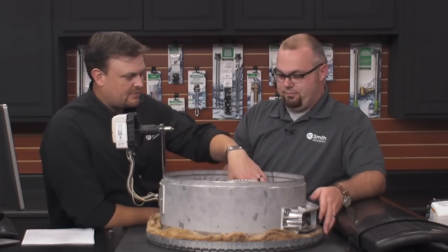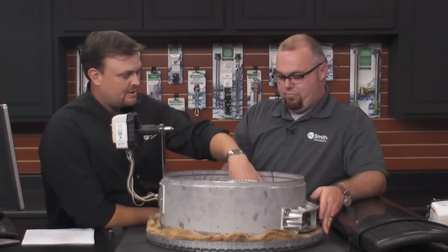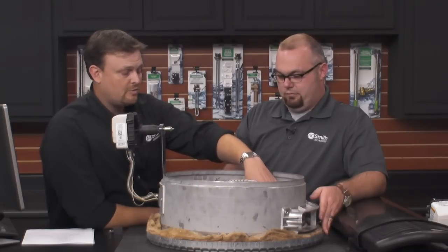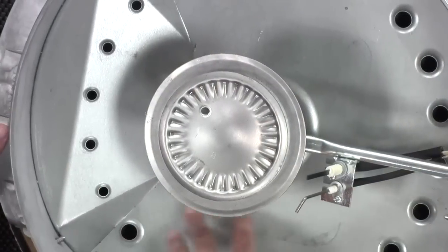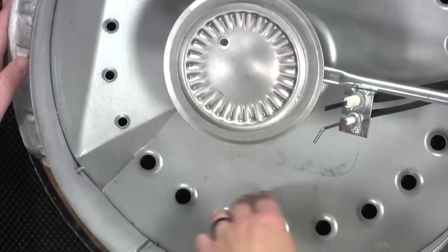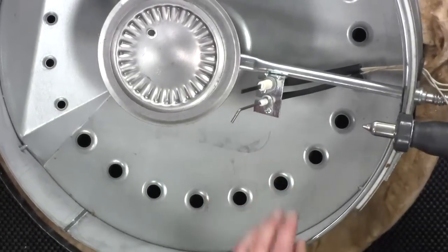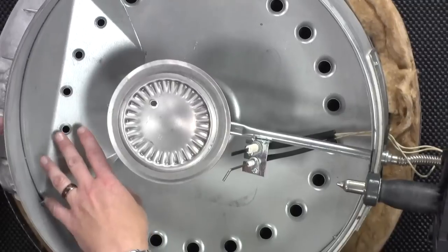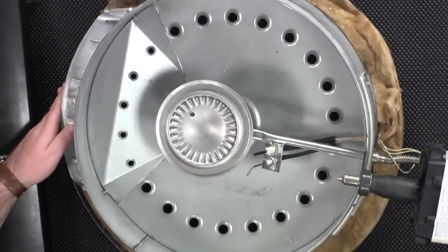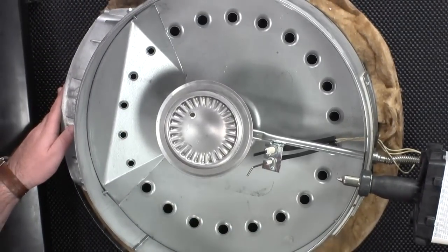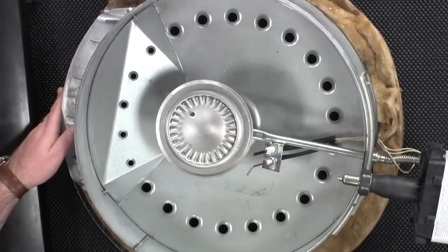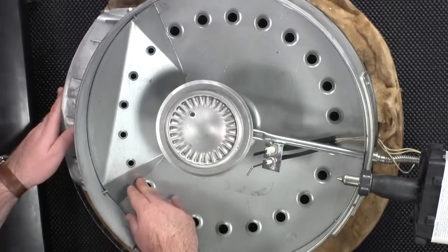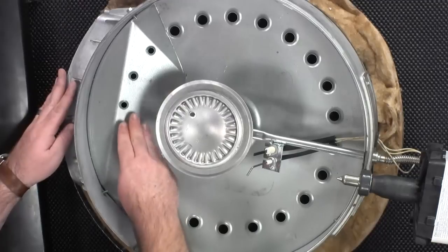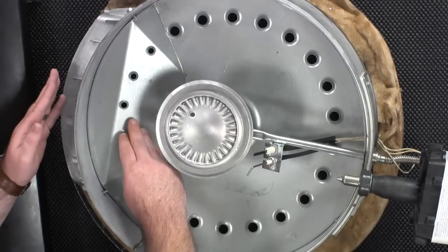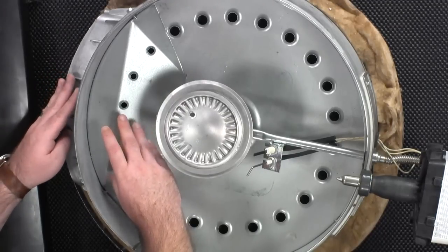And looking at the inside of the combustion chamber, and I know we can get an overhead shot of this, it's a little bit different as well. You've got all these holes here on this plate. Obviously it has to do with airflow. What's the reasoning behind that? There are actually a couple of different reasons. Depending on the way the water heater gets air, the holes closer to the vent assembly are going to be smaller. That way they meter the air, because you'd have more air right here.